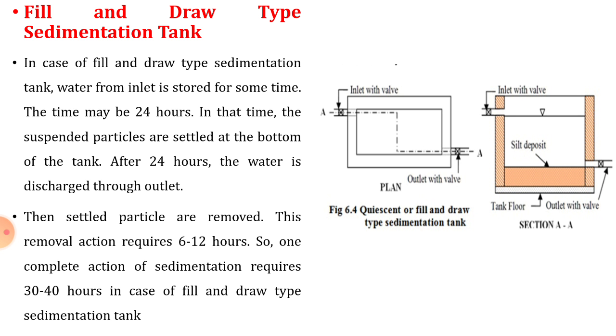In this, 6 to 12 hours are required for the removal of all settled sludge and again 24 hours for the sedimentation, so the entire cycle is of 30 to 40 hours. If fill and draw type sedimentation tanks are provided in the wastewater treatment plant, we have to make an arrangement of 3 to 4 such tanks so that the entire cycle will get continuously operated.